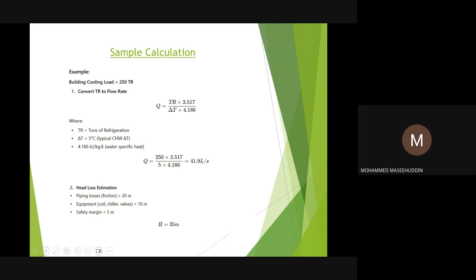So typically for any chiller, when we have the tonnage, it is easy to roughly calculate the flow rate required by the pump. And of course, for the head calculations, we might have another session. I will request our organizers of the UAE MEP team to organize another webinar on the head calculation itself, where I'll give you typical examples of how we normally calculate head for the chilled water system.